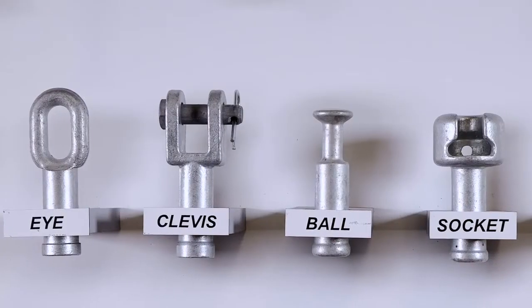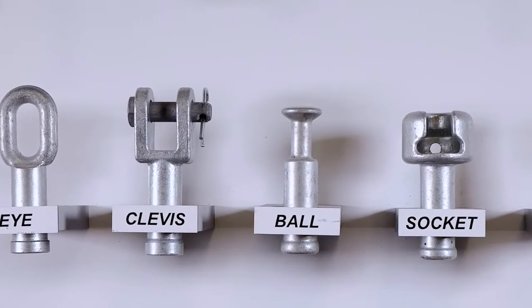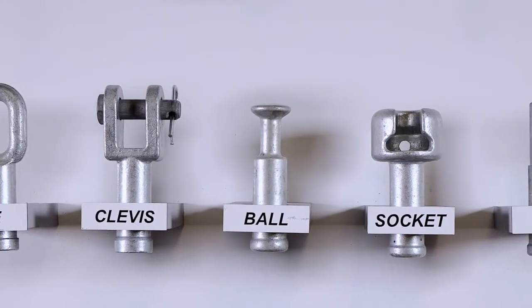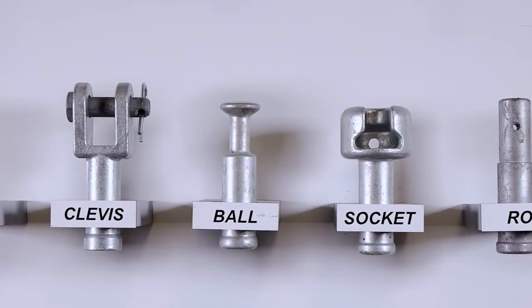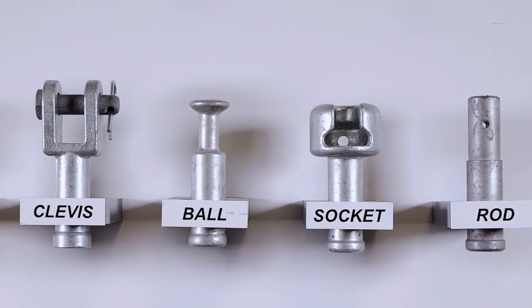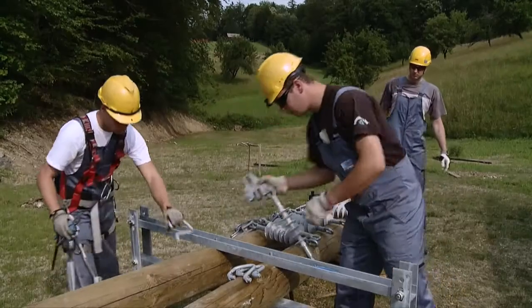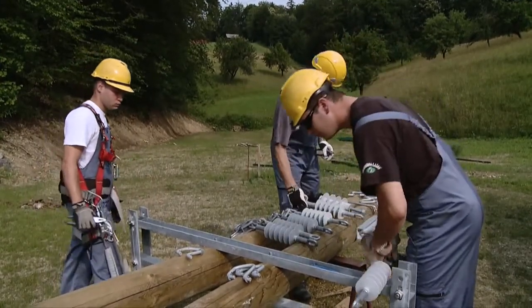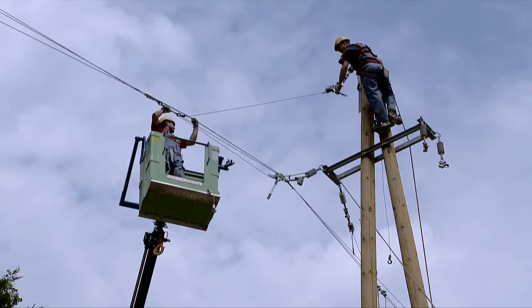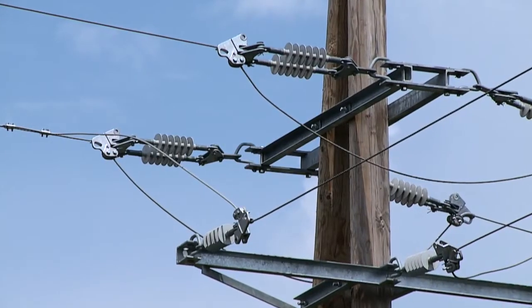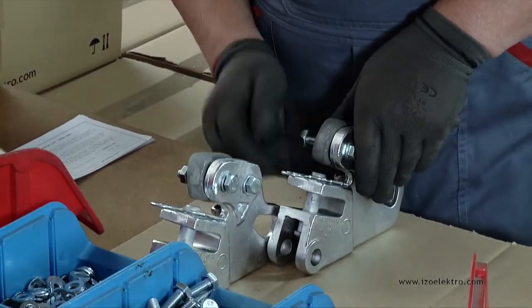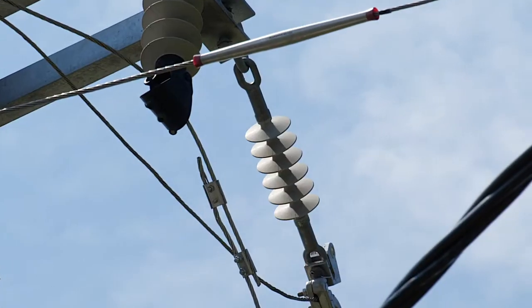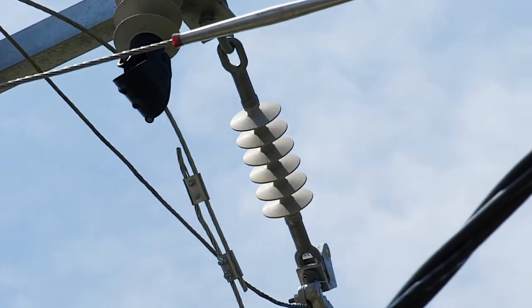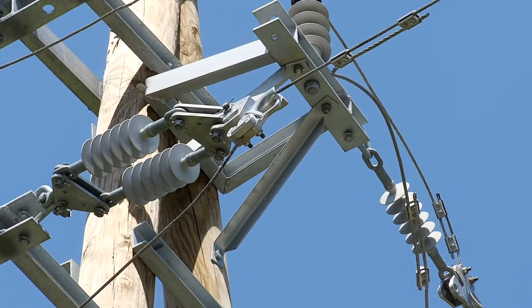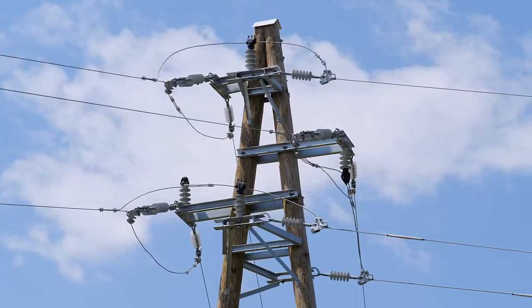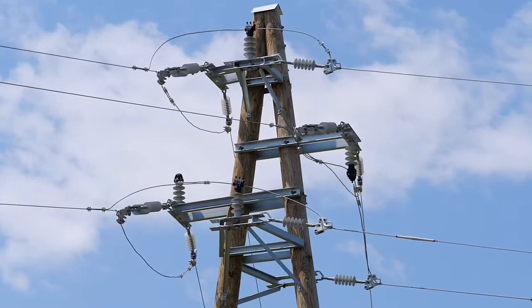Tension composite insulators are available with various end fittings such as eye, clevis, ball, socket, tongue, operating rods, and others. The universal tension clamp with 2 mutually right-angled points of application was developed and patented for the purpose of installing tension composite insulators. The shape enables the fastening of tension composite insulators into the clamp, regardless of the direction of the eye on the insulator. The use of this clamp helps to diminish the number of various types of insulators in stock.